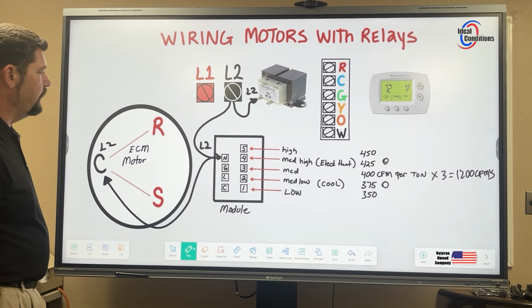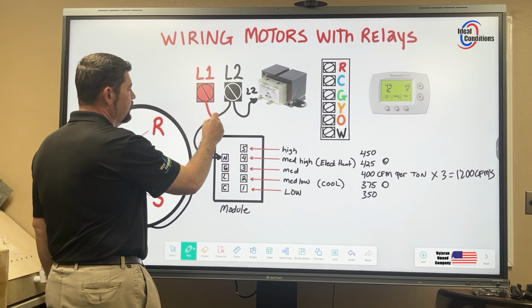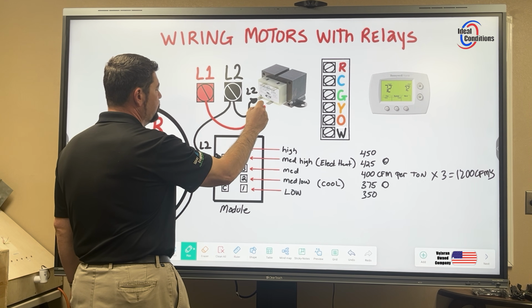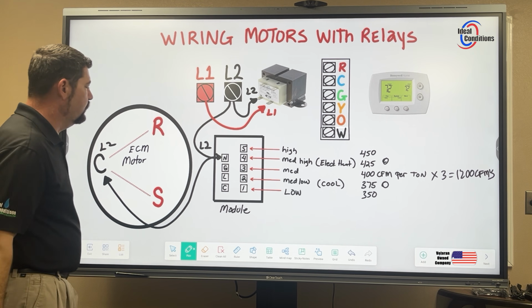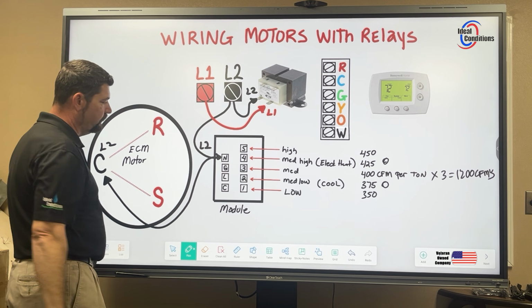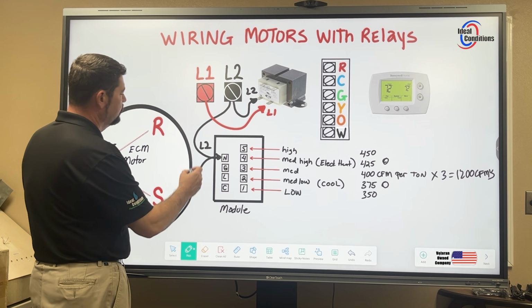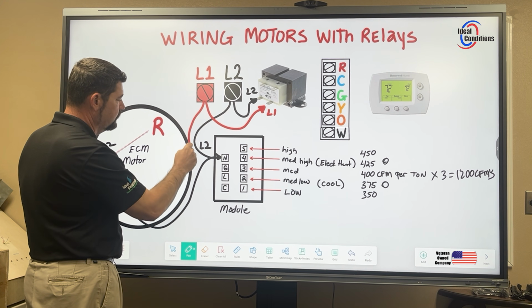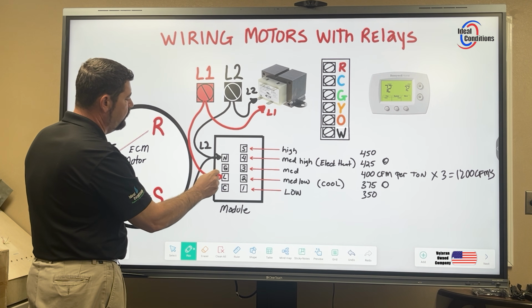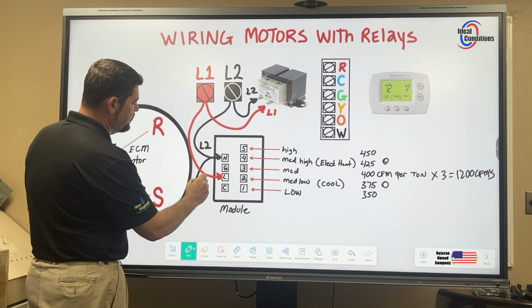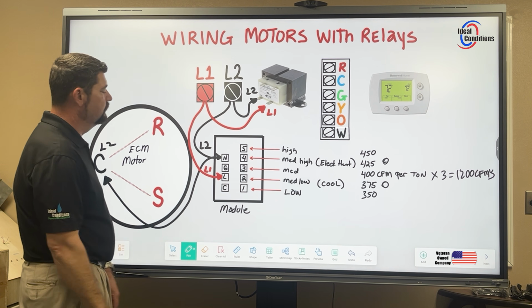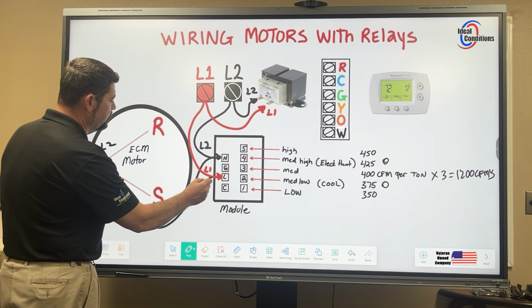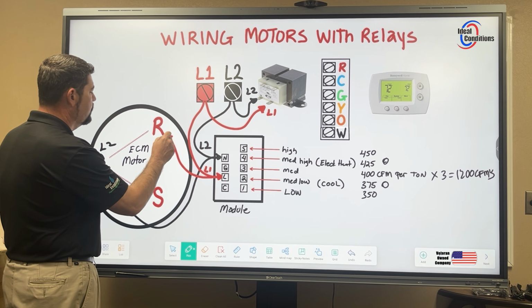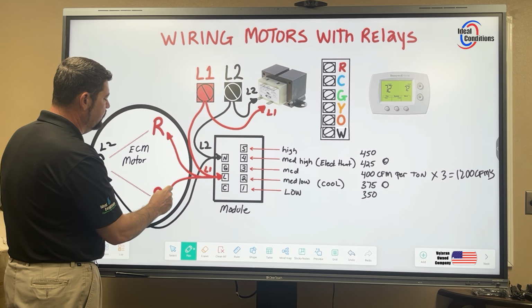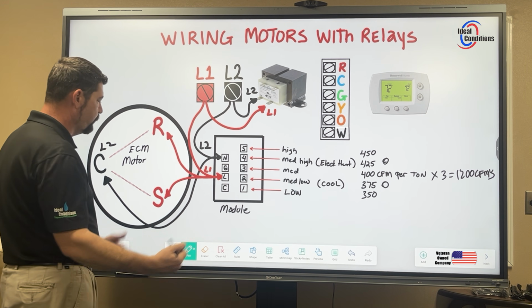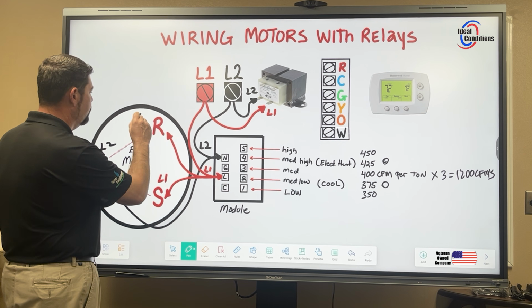We're going to go ahead and wire up L1. We're going to come off of L1, go over to our transformer, and label it L1. L1 has to make it to the motor, but first it's got to get through the module. So I'm going to come down to L for line and mark it L1. And then out of here, it's going to feed my run winding, and it's going to feed my start winding through that plug that we talked about. So I'm just going to put L1 and L1.